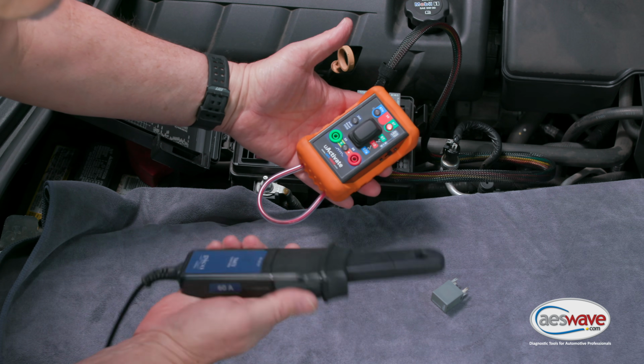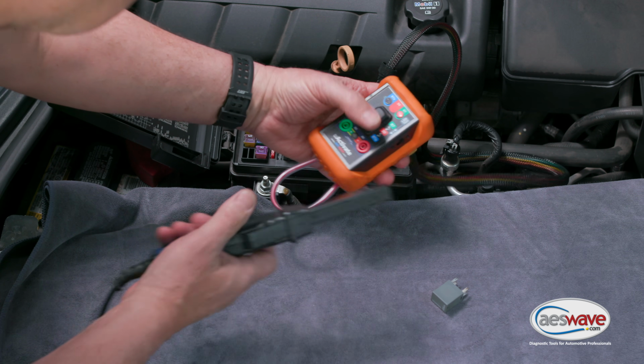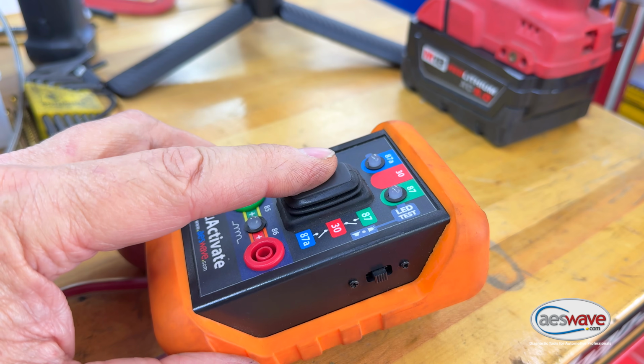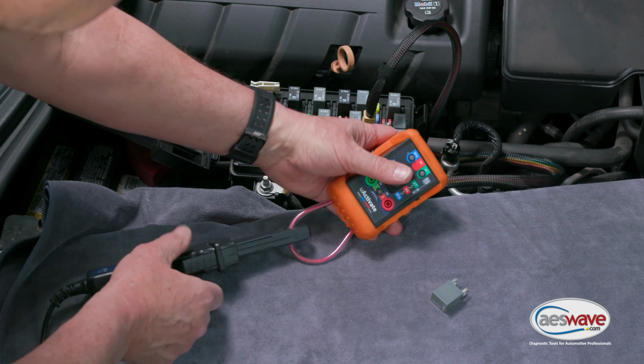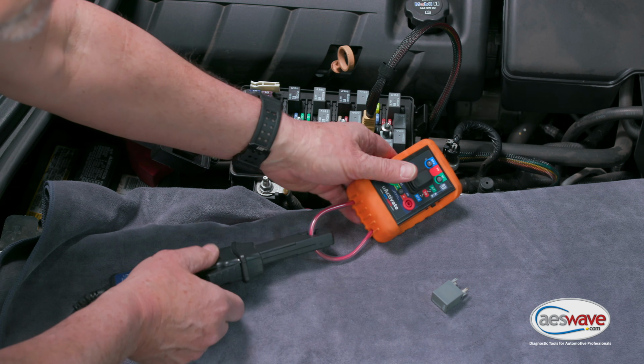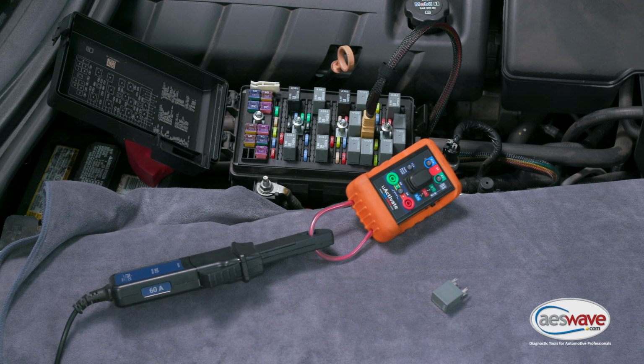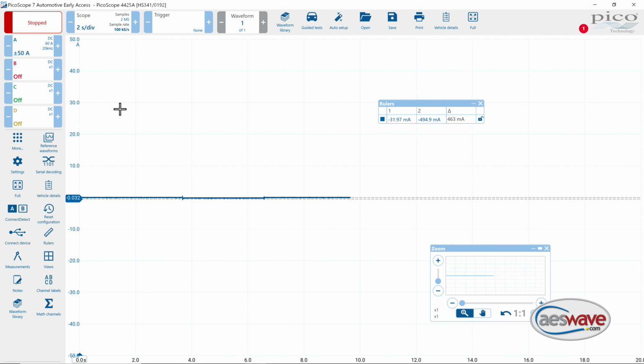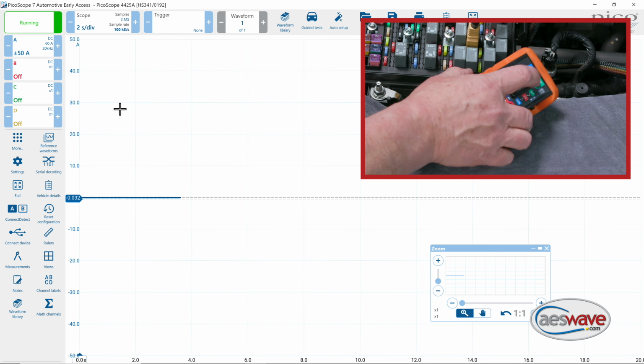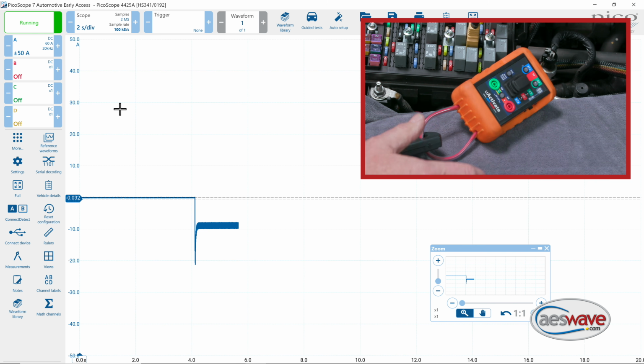Next, we're just going to install our current probe with the switch off, the rocker switch is off. I'm going to hook it around that lead, and then we're going to go to the scope, hit run. I've already set this up for 50 amps. Now we're going to hit our switch, turn our pump on, and then turn our pump off.